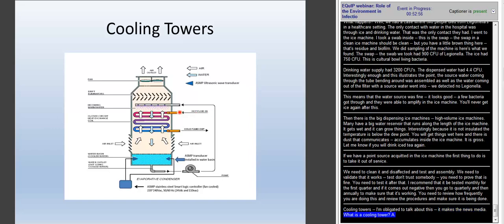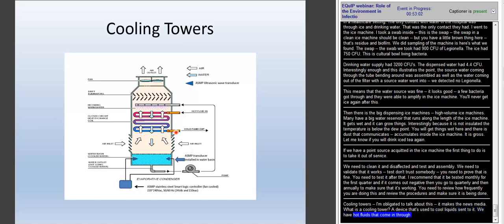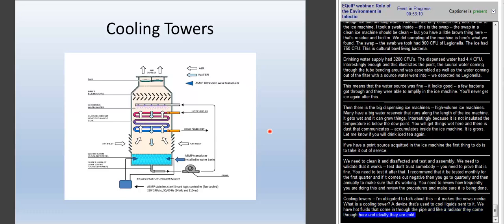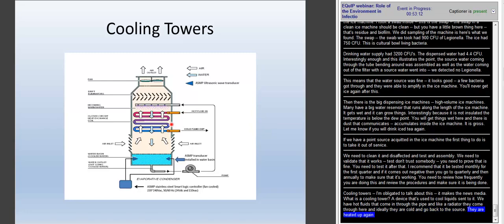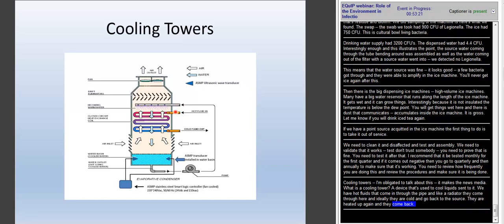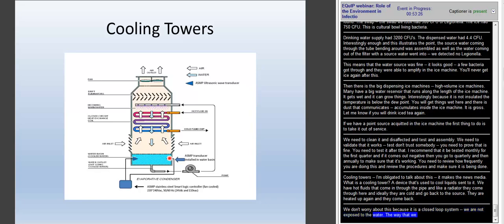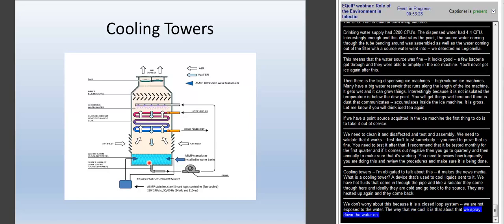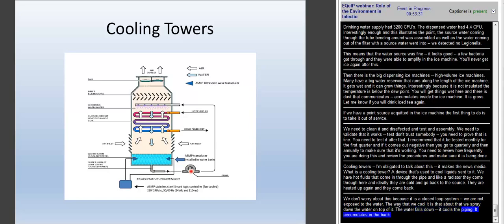Hot fluids come in through this pipe, and like a radiator, they bounce down through here, and ideally they're cooled and go back to their source, get heated up again, and come back in this loop. We don't worry about this part because it's a closed-loop system—there's no way we're exposed to this water. The way we cool it is that above it, we spray down misted water on top, and that cooler water falls down, cools the piping, accumulates in the bath down here. Then, for efficiency's sake, it's piped and pumped right back up and recirculated.